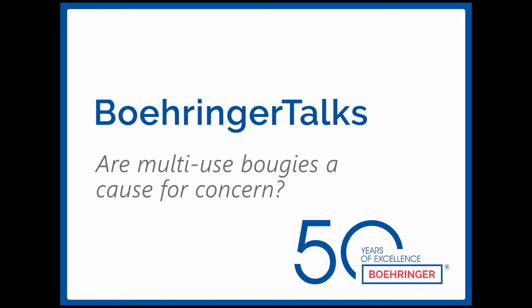Studies revealed that most hospitals do not have checks in place. They have no record of how many times bougies have been used and only replace them when the damage becomes visible. Two significant issues that arise from multi-use bougies are: number one, the shape and structure of the bougie deteriorate with each sterilization. Inspection shows that just after one wash, the surface was scratched. In addition, bougies do not retain their initial curvature with constant cleaning.